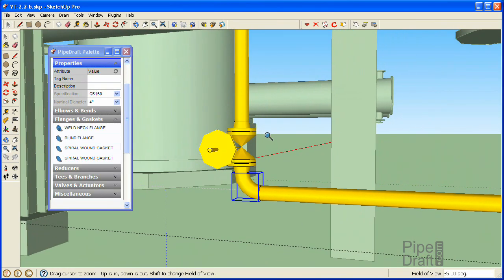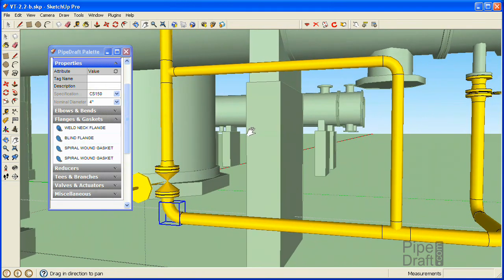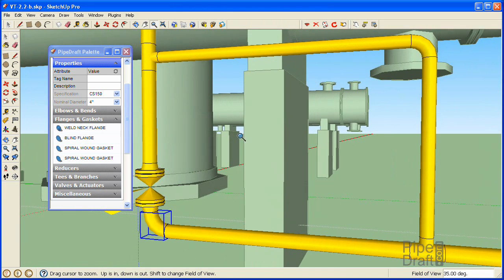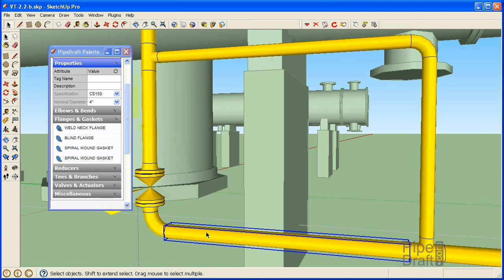Next we'll work on the horizontal side of the elbow. The P&ID specifies the need for a 3-inch nominal diameter globe valve here, so we'll need to surround it with 4 by 3 inch reducers. But first we'll need to delete the 4-inch horizontal pipe segment to open up some workspace for assembling the 3-inch fitting components. Press the spacebar, click the horizontal pipe segment, and delete it.